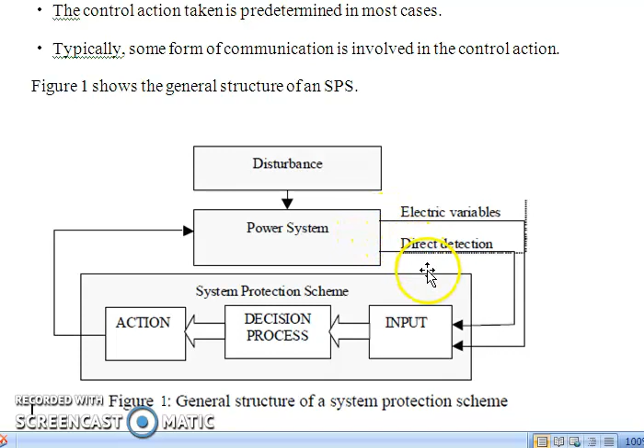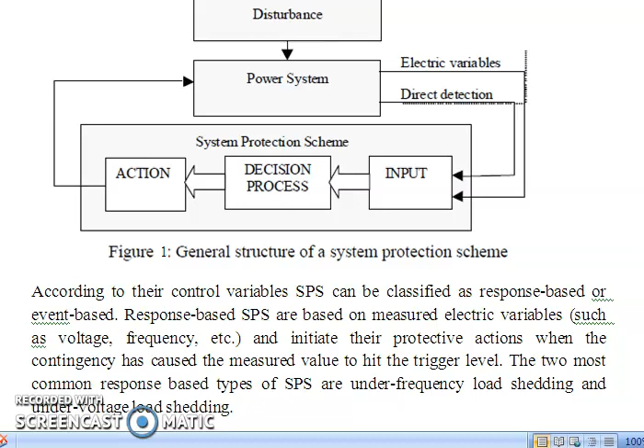Now according to their control variables, the system protection scheme can be classified as response based or event based. Fine. In case of response based system protection schemes, they are based on the measurement of electrical variables such as voltage or frequency and initiate their protective actions when the contingency has caused the measured value to hit a trigger level, that is whenever it crosses a threshold value. Now the two most common response based system protection schemes are under frequency load shedding and under voltage load shedding that we have discussed in our previous lectures.